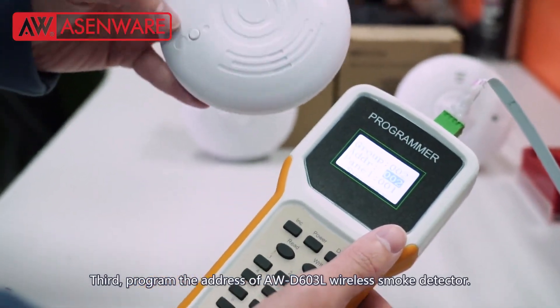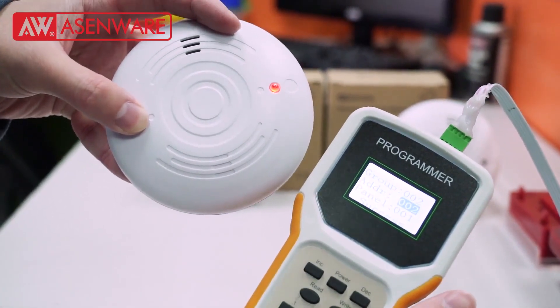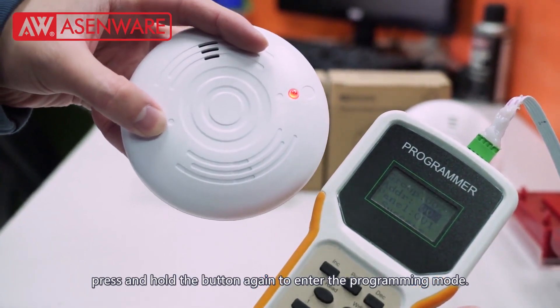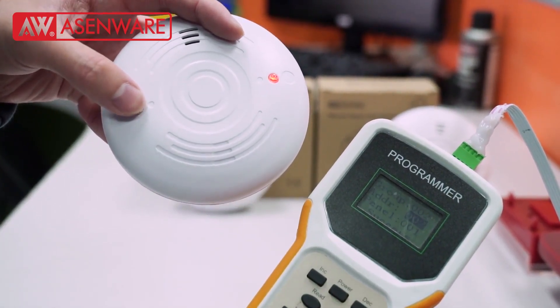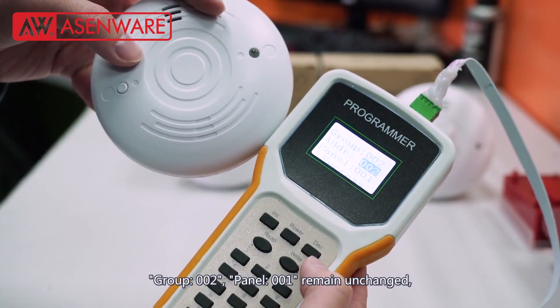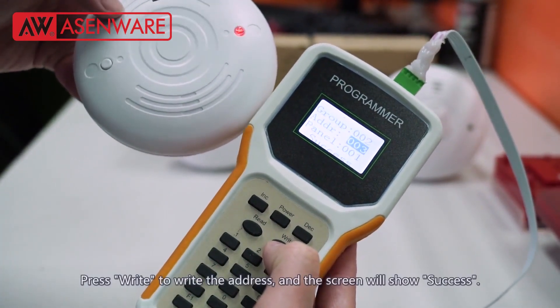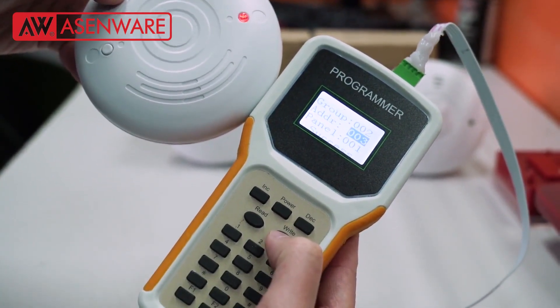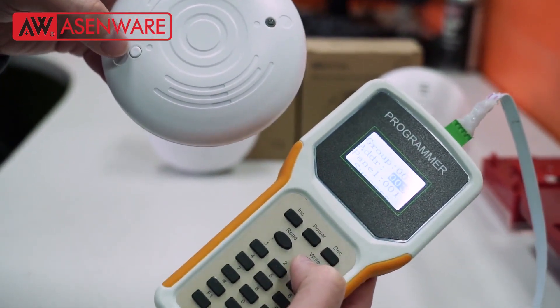Then program the address of the AWD603L wireless smoke detector. Press and hold the button of the smoke detector to turn it on. After hearing a beep, press and hold the button again to enter the programming mode. Group 002, Panel 001 remains unchanged. Press the increase button to choose address 003. Press write to write the address and the screen will show success. Meanwhile, the smoke detector will beep once. Press the button of the smoke detector to exit the programming mode.